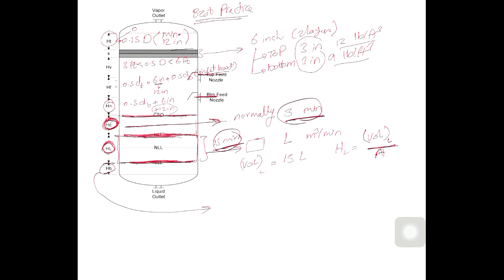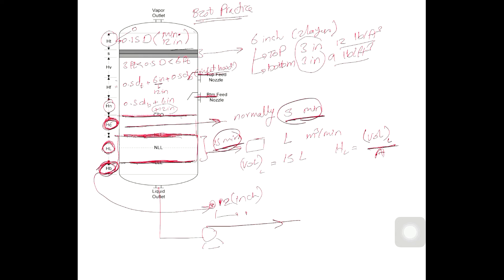The bottom space HP can be 12 inches. However, if there is a pump that sucks liquid from the separator, this value will be adjusted depending on the net positive suction head (NPSH) requirements of the pump. If there is no pumping requirement, 12 inches can be used; otherwise HP is calculated based on the pump's NPSH.